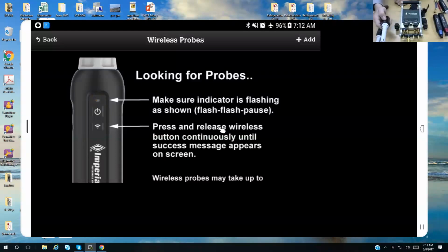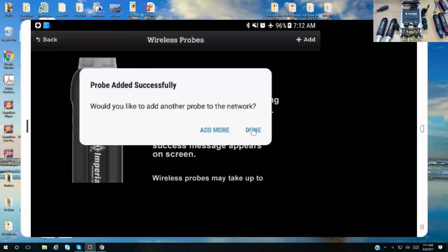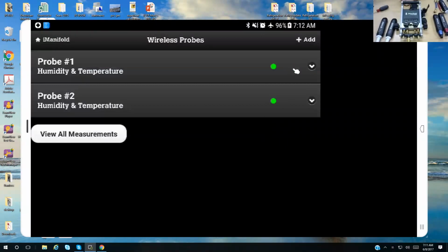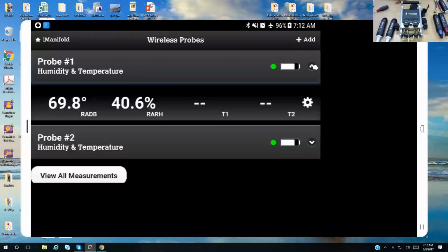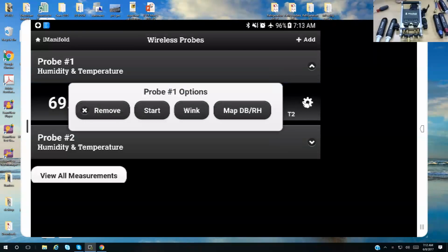You can keep adding until you're done if you're going to use more probes, more pressure probes, or humidity probes. And in this case, I'm done. It'll take us back here and it'll show the two probes. Here's our battery life. Here's the green light telling us we're okay. We can bring up this drop-down menu and see what we're looking at now. As you can see, probe 1 is set up to be the return air dry bulb and the return air relative humidity. We can change this, called mapping.